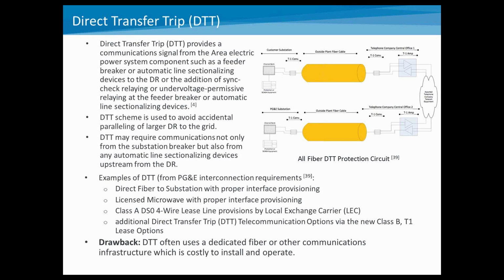If you take a look at what I had listed here from the PG&E interconnection requirements, you could use things like a direct fiber link, a licensed microwave link, or some other type of leased line. The biggest challenge is that these dedicated fiber or other communication methods are often costly to install and operate. So for large-scale systems, say on the order of 20 to 50 megawatts of distributed generation, you may be able to absorb the cost of a communication system into that project. For smaller systems, it's going to be difficult to be cost competitive to allow that kind of a system to be installed if they don't already have some kind of communication mechanism.